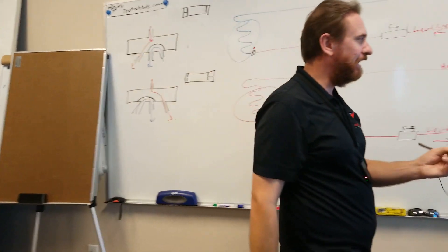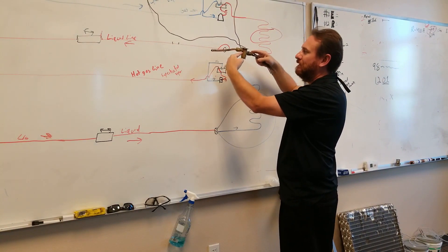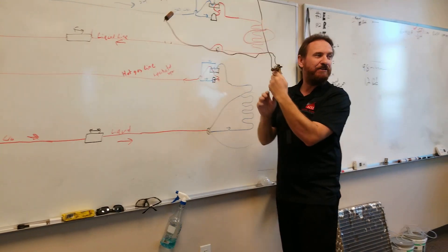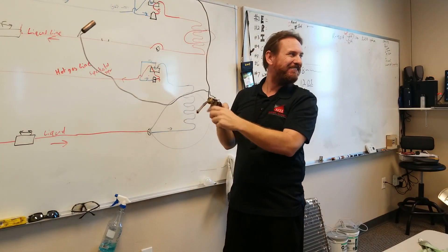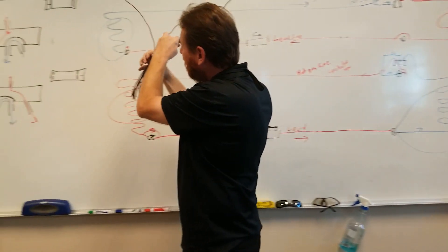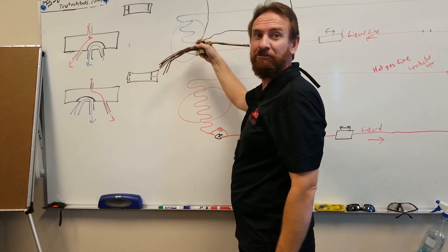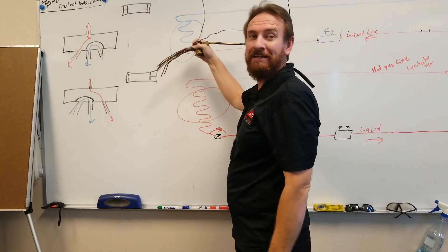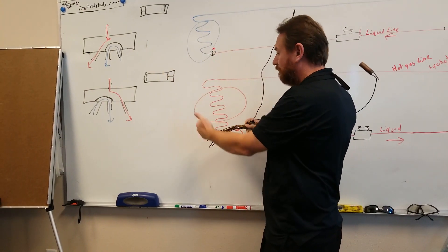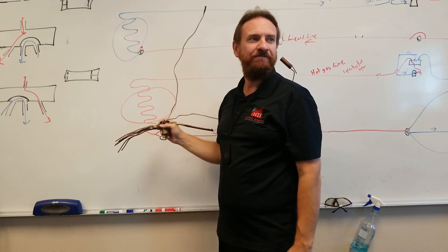I can also put this component outside — I just turn it around. As refrigerant flows one way, it's being metered; as it flows the other way, it's being bypassed. In the summertime, with it turned this way, is it metering refrigerant and monitoring superheat? Yes. But the same valve in the wintertime is doing nothing — it's bypassing like it's not even there.